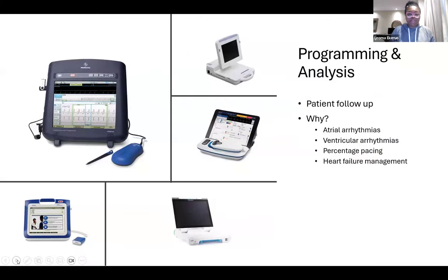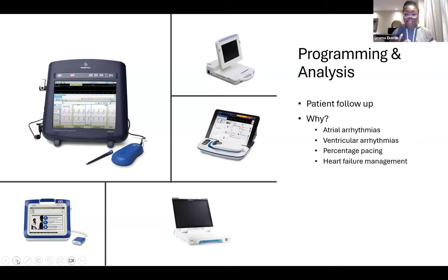For programming, there are many device choices. The most popular in Nigeria and sub-Saharan Africa is Medtronic — they have a huge presence. But remember patients travel abroad and may get devices that are not Medtronic. You definitely need to ask the patient what kind of device they have, because you need the right programmer to check it. If you don't have the programmer and the patient is having issues, please reach out so we can figure out exactly what's happening or how to get the patient checked — we're gathering that information in a database.